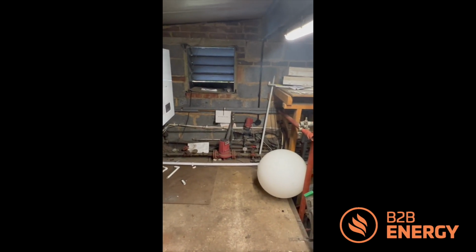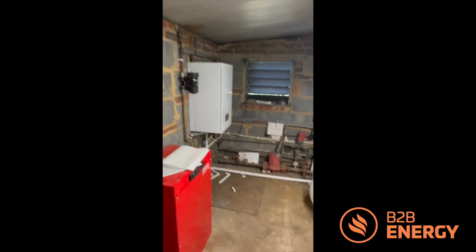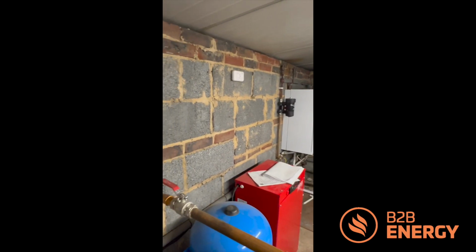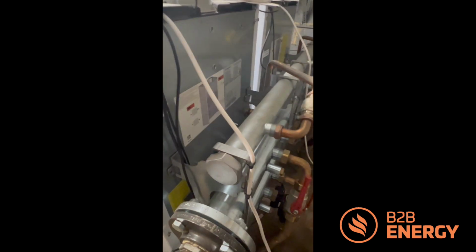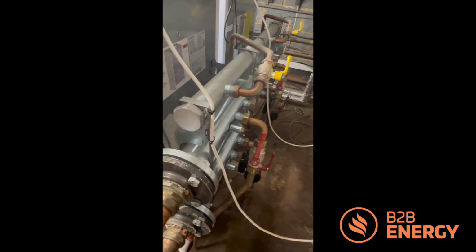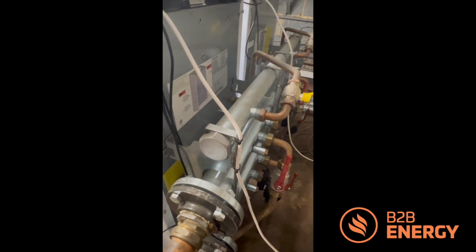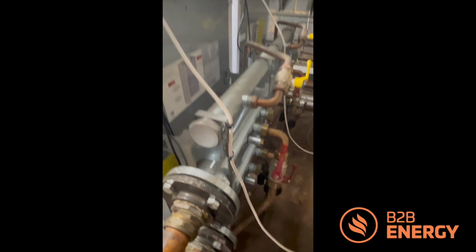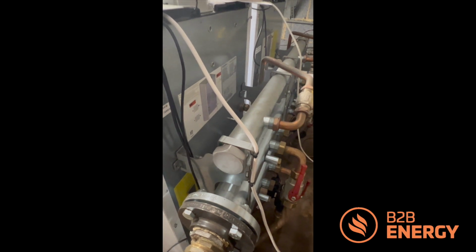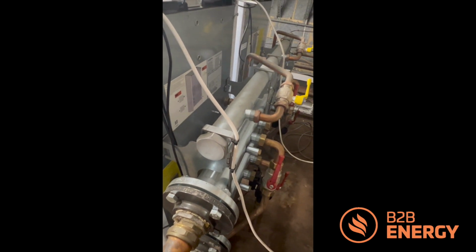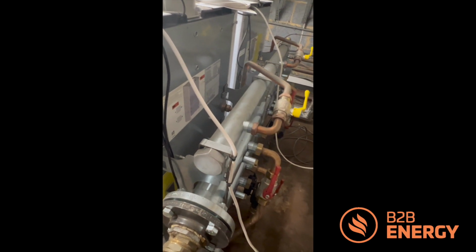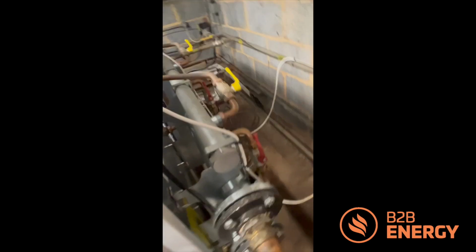These areas don't need to be lagged, and you can see in general areas there's no leaks that can be identified. When we look behind the boilers we can see the heating flow and return coming out of the boiler, which clearly shows that this hasn't been lagged. This is an opportunity to start to identify with our thermographic camera that there's some lagging that's missing.